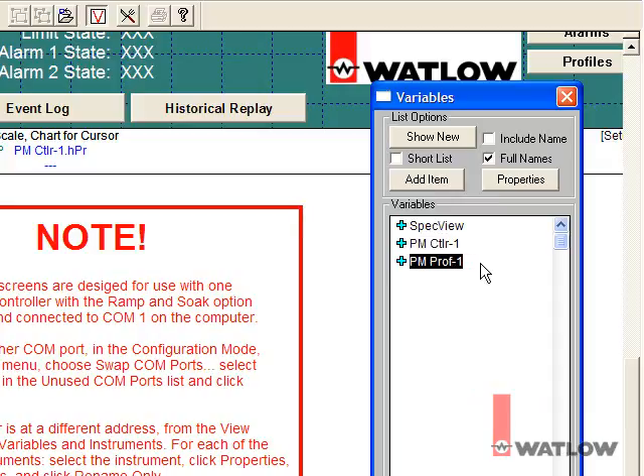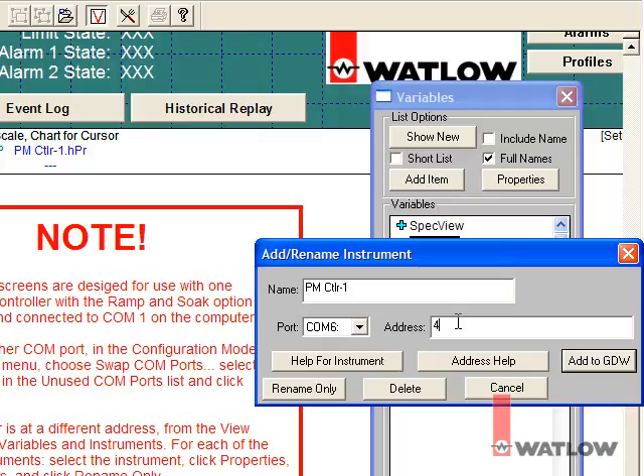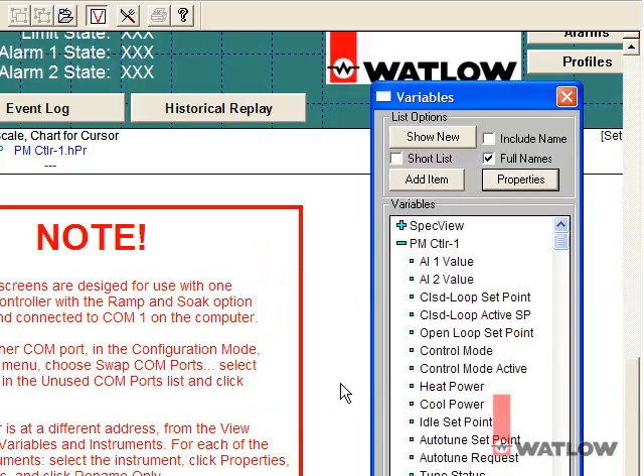To change an instrument's address, select it and click Properties. In the Add Rename instrument dialog, you can rename the instrument, change the COM port on which SpecView will attempt to communicate with it, and change the address. Because my controller's at address 4, I'll change the address from 1 to 4. Click Rename only to save the change.